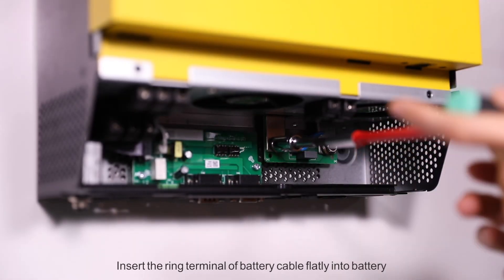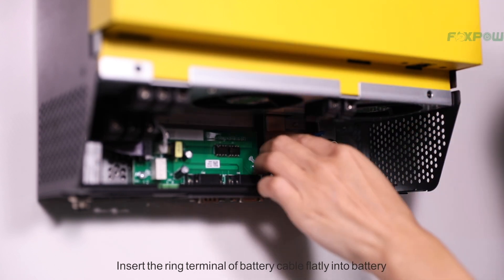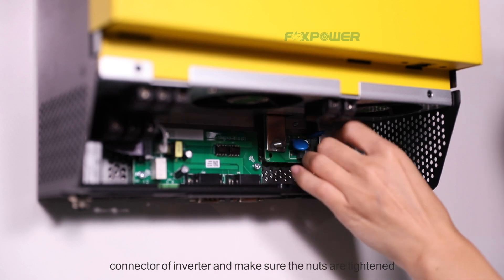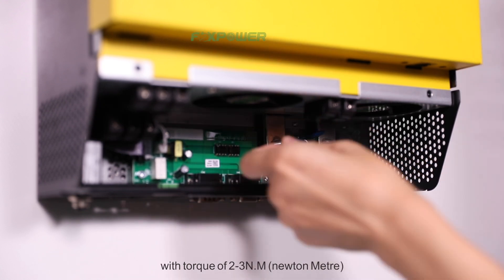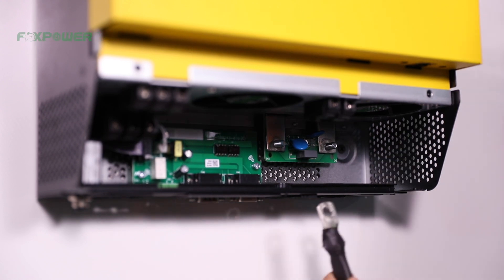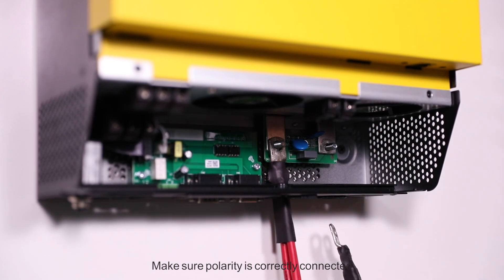Insert the ring terminal of the battery cable flatly into the battery connector of the inverter. Make sure the nuts are tightened with a torque of 2 to 3 Nm. Make sure polarity is correctly connected.